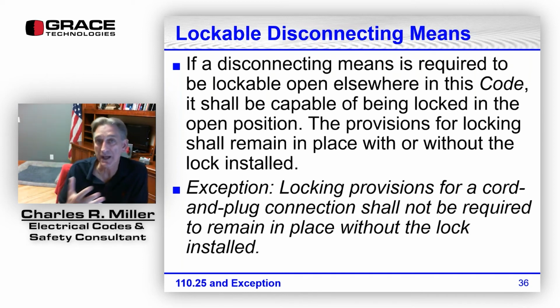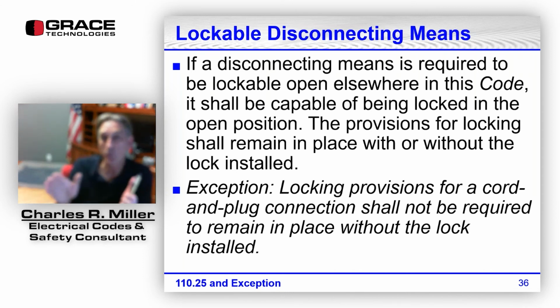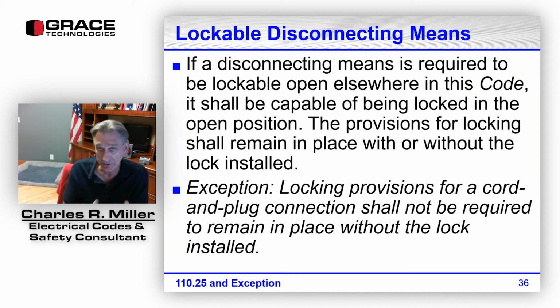Every section, for example, motors. The general rule for motors is a motor has to have a disconnecting means within sight of the motor. That's the general rule; Article 430 tells us you have to have a disconnecting means within sight of the motor. There's an exception. It says, if the motor has a disconnecting means that is capable of being locked in the open position, then it does not have to be within sight of the motor.